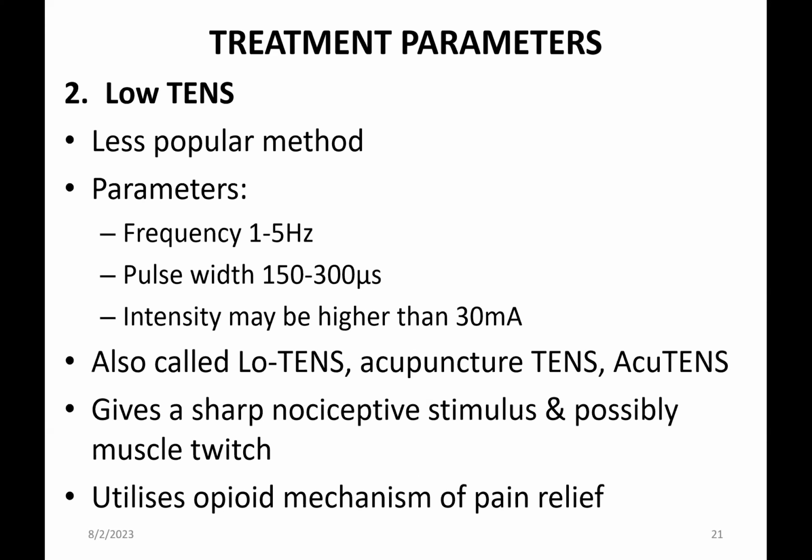So the low TENS will use lower frequencies. Typical range is 1 to 5 hertz, but this range could also be extended to include up to 10 hertz in certain circumstances. And the lower the frequency, the higher the intensity, which is about 30 milliamps in this case. So this one, because you use a slightly higher intensity, tends to produce a nociceptive sensation in the patient, and this is what the patient will give you as feedback.